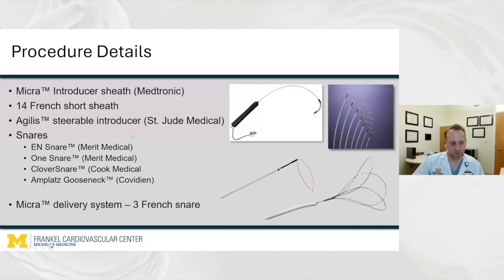The second approach would be using the Micra delivery system itself. So if you have just implanted the device and pulled the tether out, and decide you want to get it out for whatever reason and don't want to use any more tools, you can use the Micra delivery system. It's significantly more challenging because of the limitations of the system itself. You can fit a snare through the tether port in the device itself, but it has to be small in order to fit, and that makes it a little more challenging. The best way to do this is to use the cup of the delivery system, try to get it over the back end of the Micra itself, and then snare that proximal retrieval feature with the tiny little snare while you have control of it with the cup.